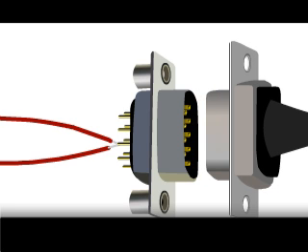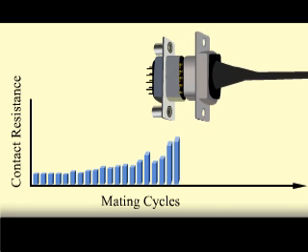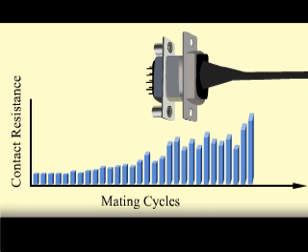So a 4-wire fixture that uses a mating connector will still include the resistance of the mating pins, usually 10 to 100 milli-ohms. And as the pins wear out with continued use, this contact resistance will increase and become more variable.